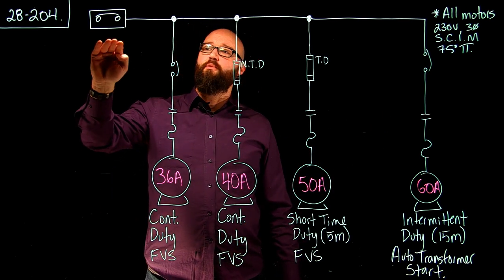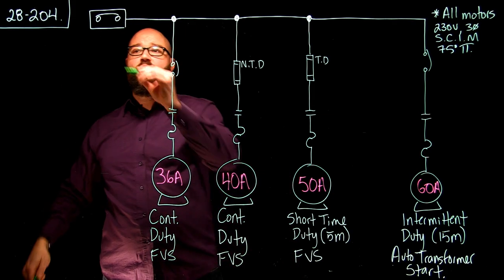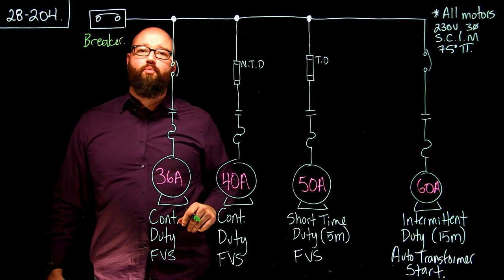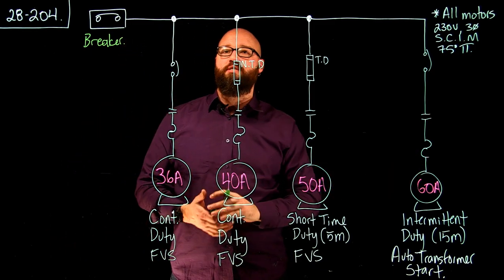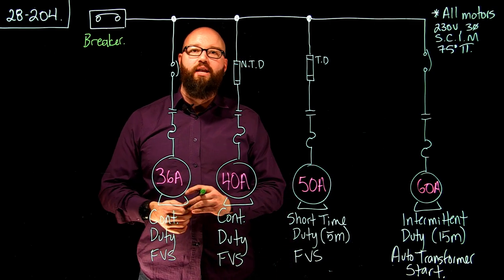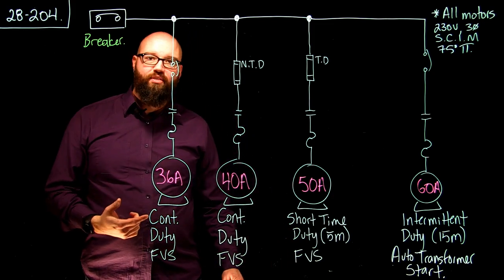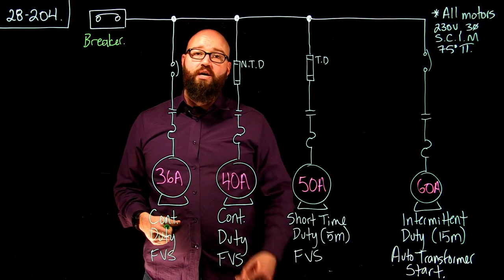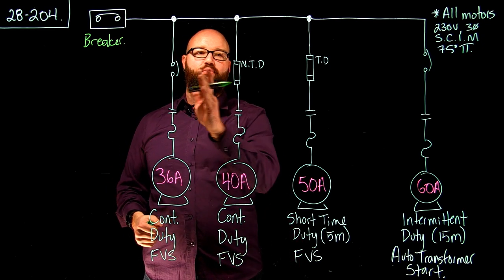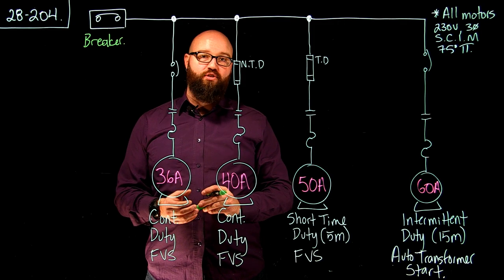We're going to use the multiplier for what the main overcurrent device is — in this case, we have a breaker. So every time I use Table 29 for each one of these individual motors, I'm going to apply the multiplier for a breaker. When we use Table 29, what we're concerned with is: what type of motor are we dealing with, what is the starting method of the motor, and what is the overcurrent protection device.